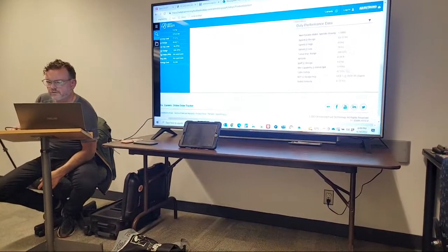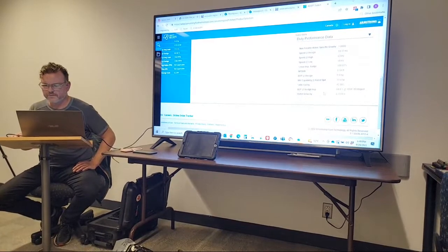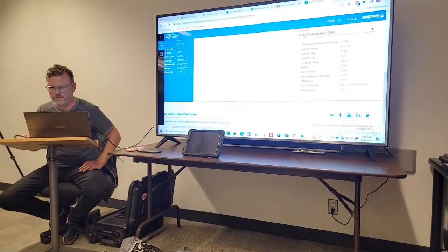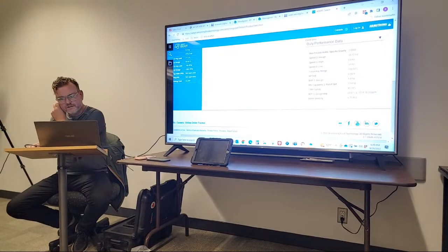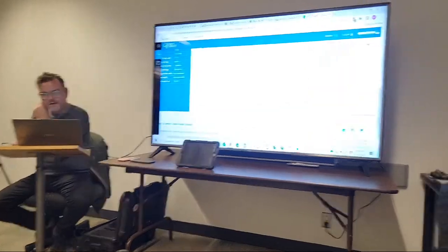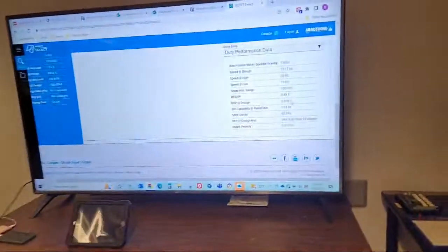This is running at constant volume, right? So you can sort of see motor capability rated, motor design. So your brake horsepower is the actual work that's happening. So that's the net positive suction head. So you don't want to drop below there, you'll cavitate your pump. But that's 9.4 horsepower. It was a 15 horsepower pump that's there.